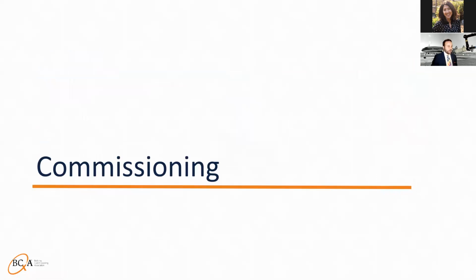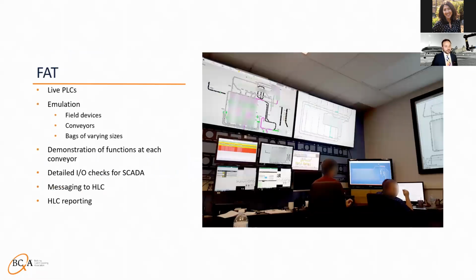Now we'll go into some of the main commissioning steps. One of the highlights of a baggage handling project is a factory acceptance test. Often, these will use live PLCs with the actual code that will be running out in the field with emulated systems behind them. The baggage handling mechanical components will be entirely emulated with the correct length of conveyors. The system will send bags of varying sizes down. Also emulated are photo eyes and encoders, and they'll send pulses at the right speed and become blocked when the virtual bags pass over them.